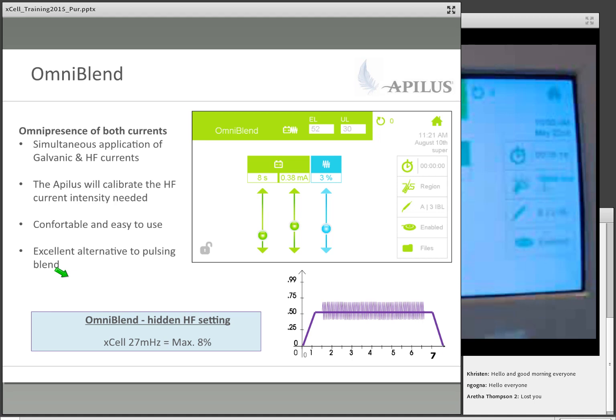Omni blend is our other type of generic blend, or normal case type of blend. Omni blend is galvanic, and again, you see galvanic doesn't do much different here. It just does a little trapezoid shape and goes off. Our time is 8 seconds. Our MA is 0.38. But the thermolysis is different in this case. Whereas with Pico blend, it was delivered in pulses, now we just have continuous. So all you're seeing is the 3% because the timing is essentially almost the whole duration of the pulse. So in the graph, you can see it as a continuous high frequency pulse at very low settings.